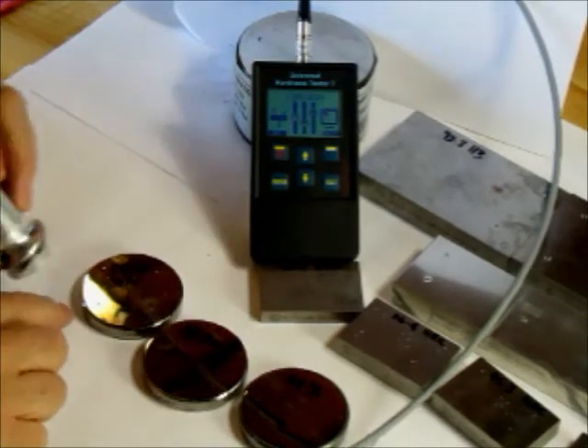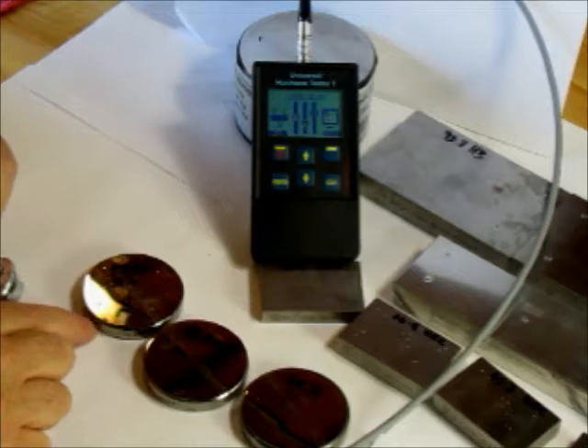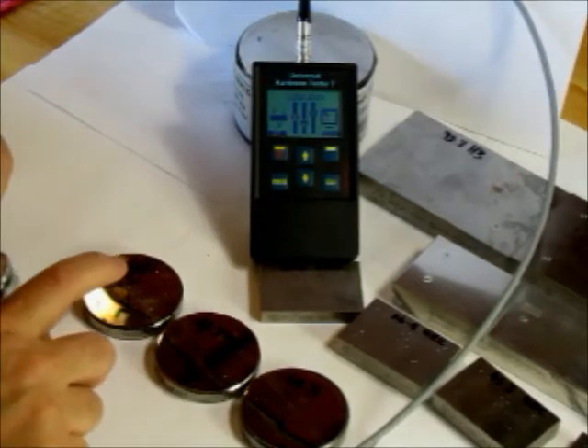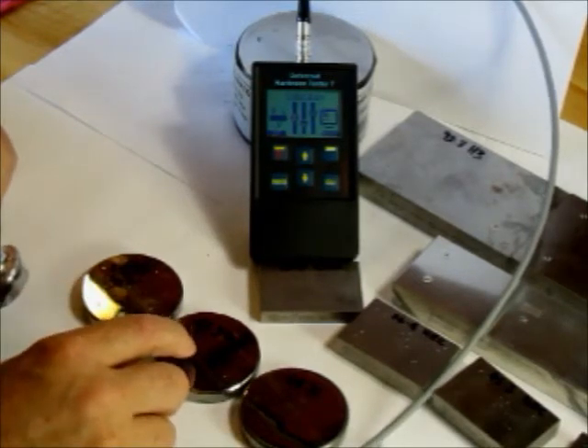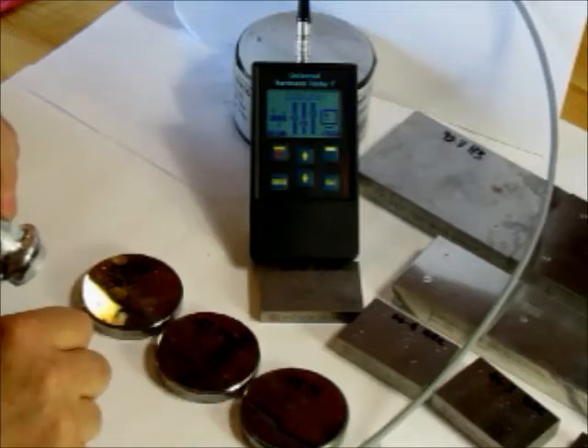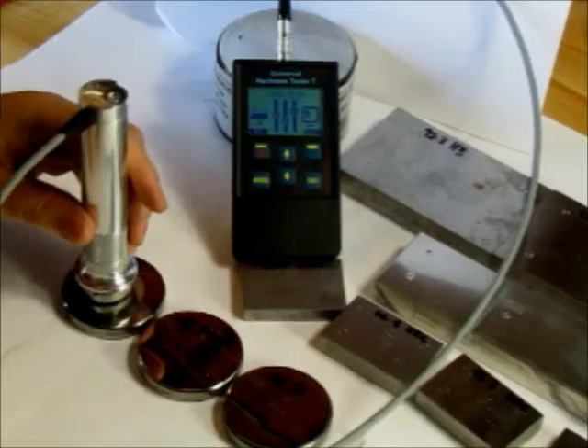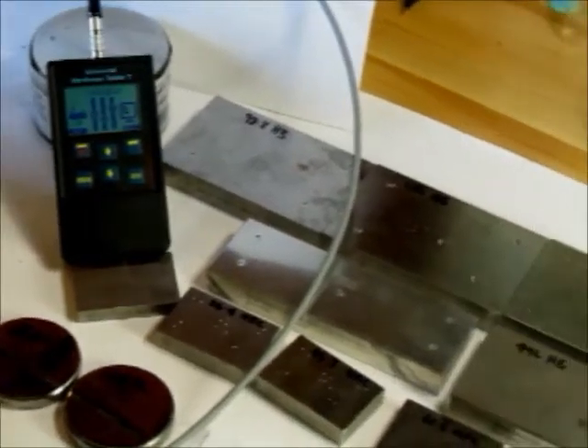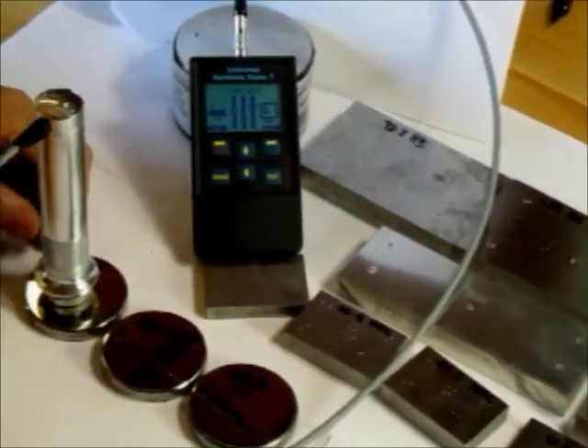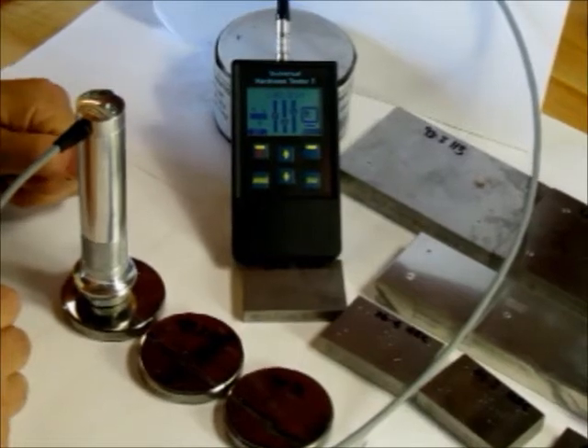So I have 3 NIST certified calibration test blocks here. This is a 23.17, 47.3 and a 64.3. Other test blocks are shown over here for Brinell and so on. This tester can be calibrated and needs to be calibrated for Rockwell C, Brinell and Vickers.